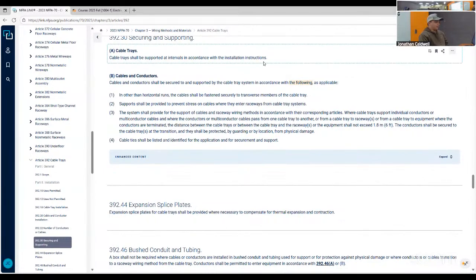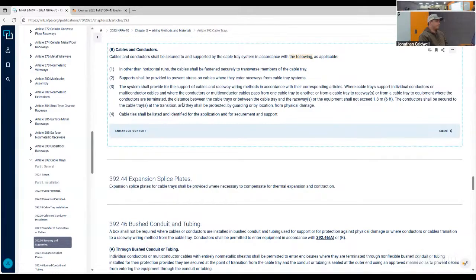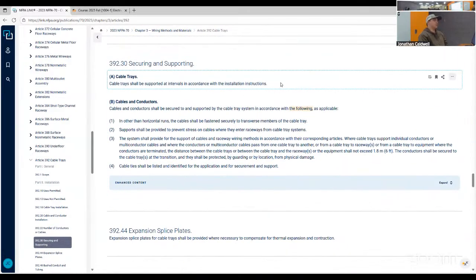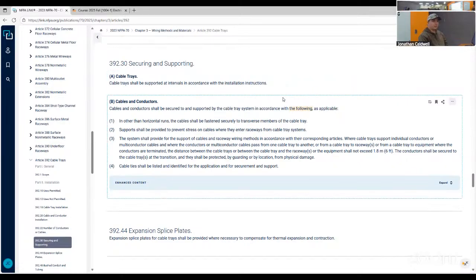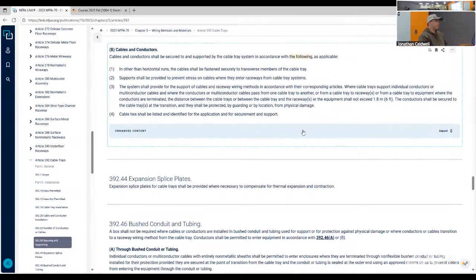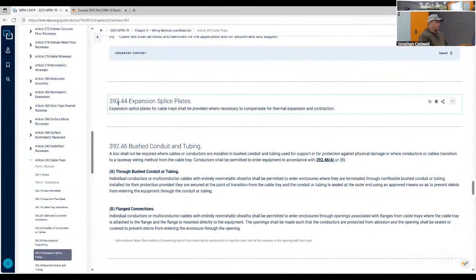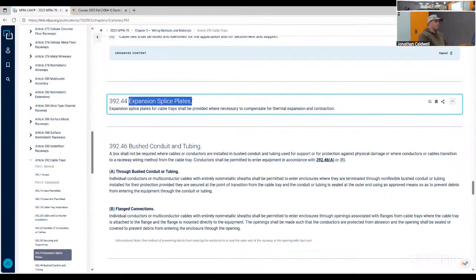But then cable trays shall be supported at intervals in accordance with the installation instructions. Every single manufacturer has different installation instructions. They try to make it easier for everyone and try to be similar, but there are usually those little niche things about them. And then you do have to install expansion splice plates. Now, out at Simplot, we don't do the typical expansion splice plates, because we did an install with expansion splice plates and the splice plates ended up just breaking apart out there, because the expansion and contraction is just so much for them. And really, all they are for the tray we buy is just elongated holes, so they don't really do anything.